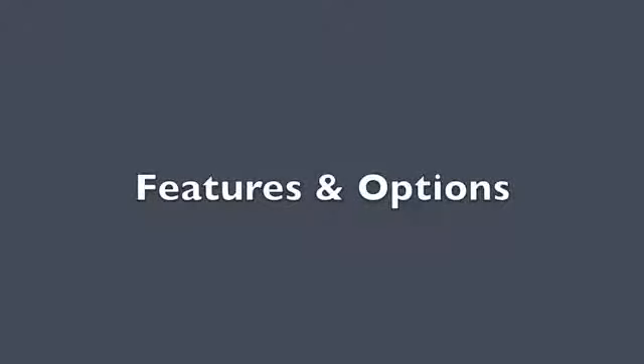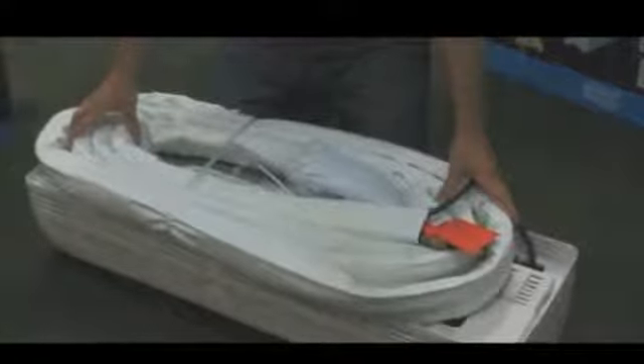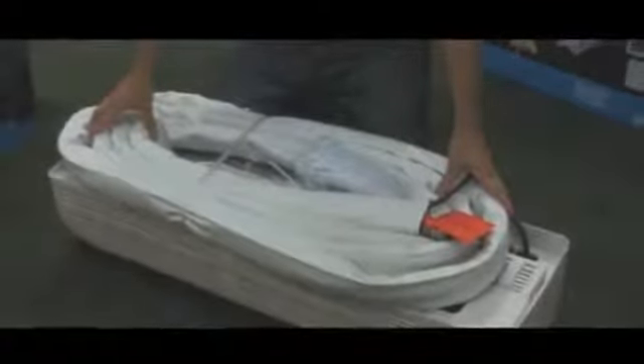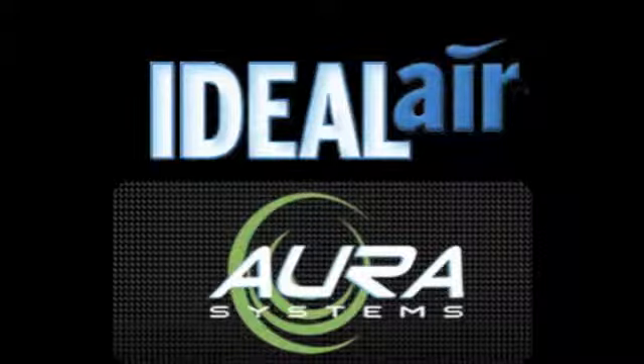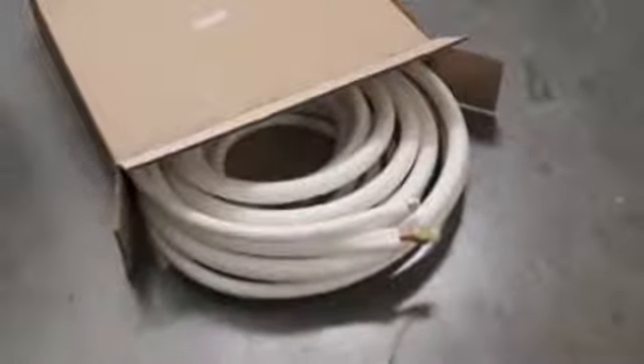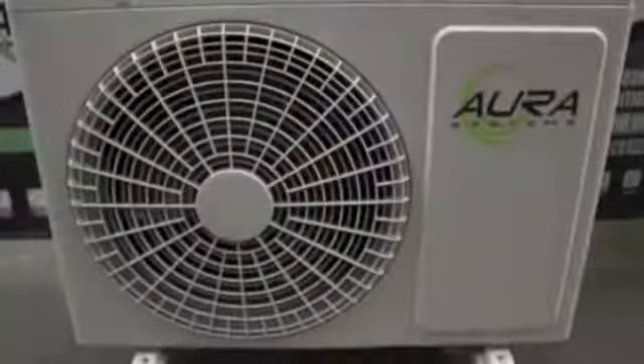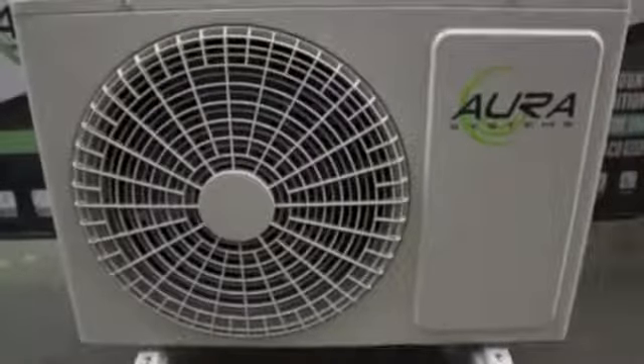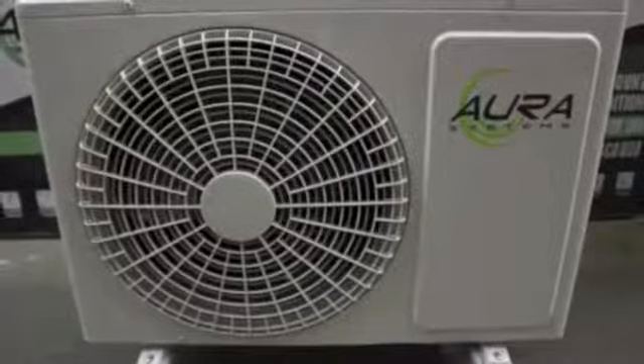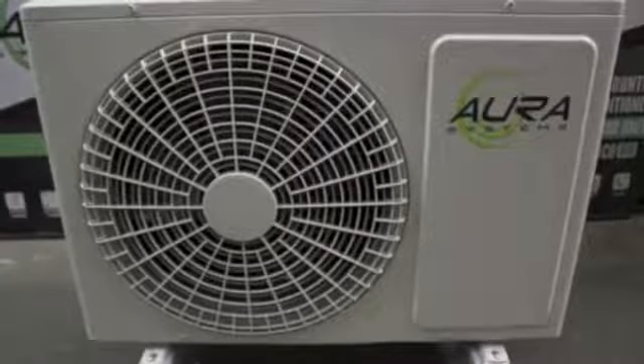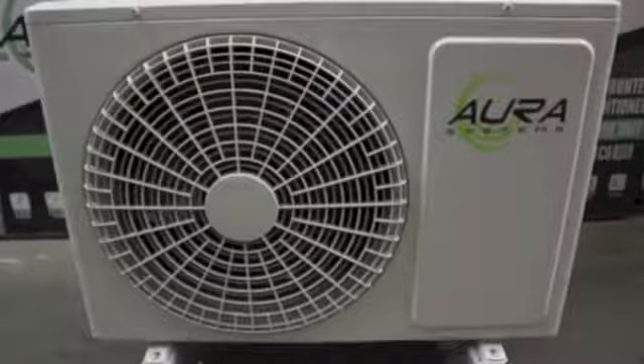Some things to really look for when you're buying a unit. One first option that can be on some units, and is really popular, is known as Quick Connect, with pre-charged lines. Now, Ideal Air and Aura Systems offer this option, and what this option allows you to do is install your unit by yourself instead of having an HVAC or AC service professional come and do it for you. So in non-Quick Connect units without pre-charged lines, an HVAC professional must come out with a vacuum that purges the lines, which can then be connected to the two units, and then the unit can be turned on. So in Quick Connect units, these lines are filled up with the refrigerant, and the unit can be turned on after the lines are connected and the necessary installation procedure is followed.